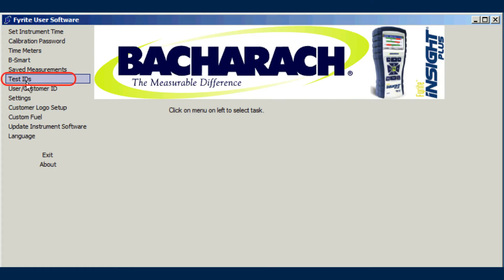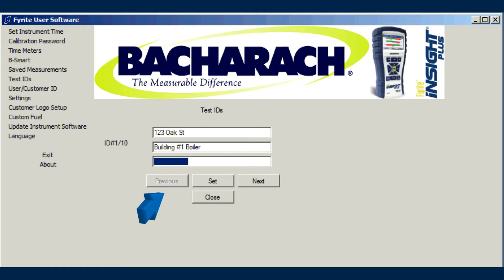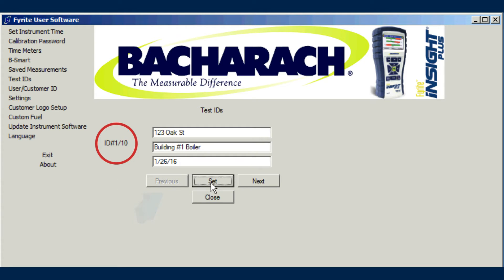Use the Test IDs menu item to read test ID information from the analyzer and to enter and download new test IDs to the instrument. Using the software may be more convenient than using the instrument's keypad to enter test IDs. Use the Next and Previous buttons to scroll through individual test IDs. Press the Set button to transfer the current test ID to the instrument.